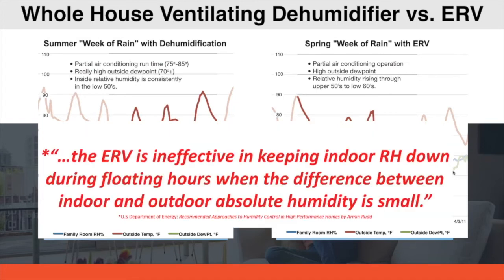And Armin Rudd did a study with the DOE that basically supported that ERVs are ineffective in keeping indoor RH down during floating hours, when the difference between the indoor and outdoor absolute humidity is small. So if it's humid outside and it's humid inside, there's going to be very little latent exchange going on in the core of that ERV. It's really when you have larger delta Ts between that you're going to get more moisture removal.